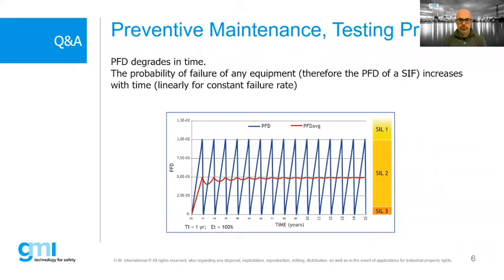Preventive maintenance and proof testing is also important. For those who already participated in functional safety activities, this is the graphic that shows how the probability of failure on demand increases with time. When you start operating today with a power supply which is maybe certified for SIL 3, by the time the certificate is no longer valid, you will go out of the SIL 3 band, and go to SIL 2 and then SIL 1 again. So preventive maintenance and proof testing activity is very, very important to keep a certain level of safety in your application.